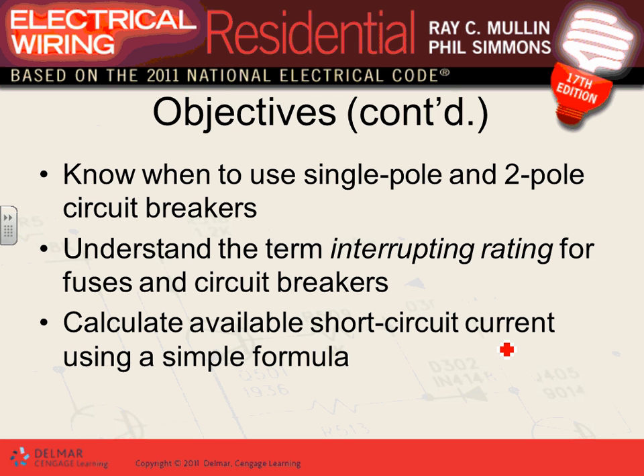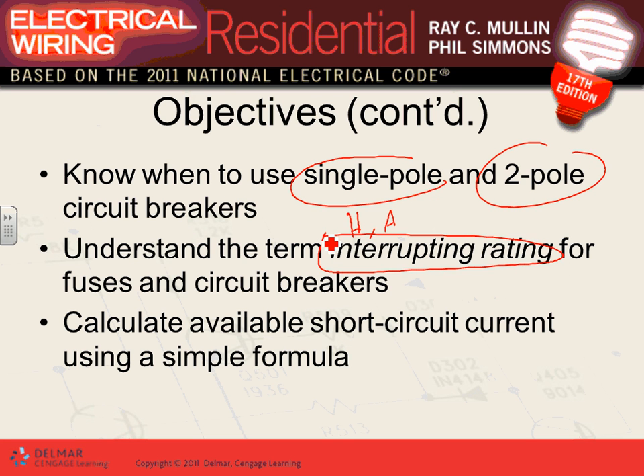Every time we talk about a single pole, this is a phase or a hot. Two poles is two phases and two hots for circuit breakers. The interrupting rating of circuit breakers is very important — you need to understand how much a circuit breaker can interrupt under normal operating voltage for that system.